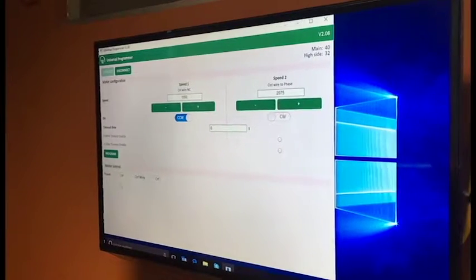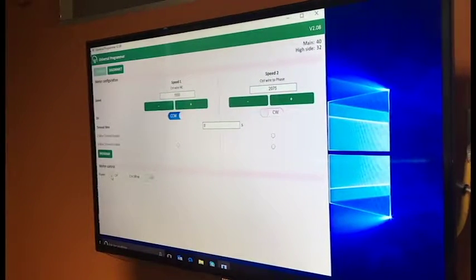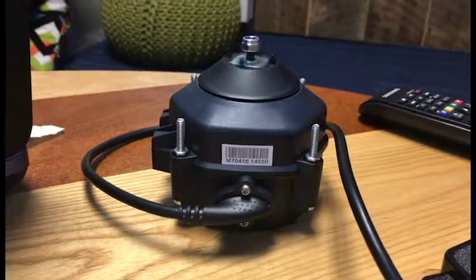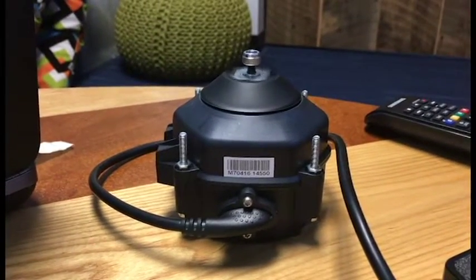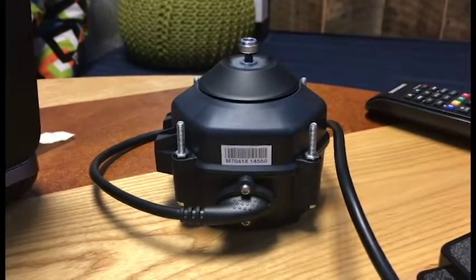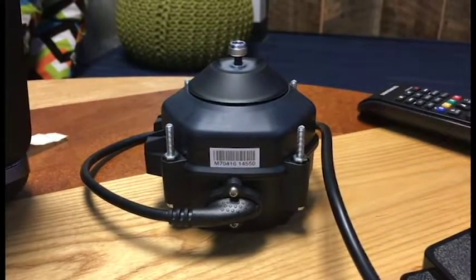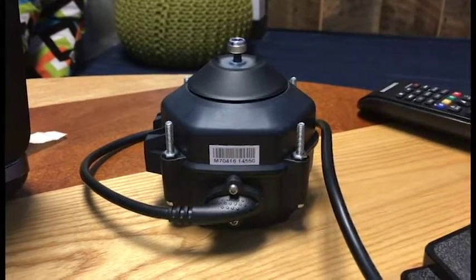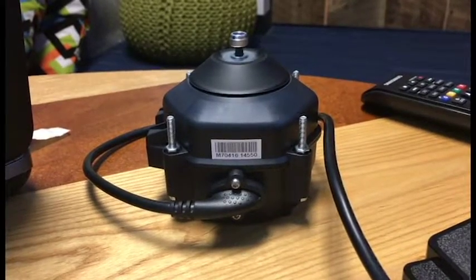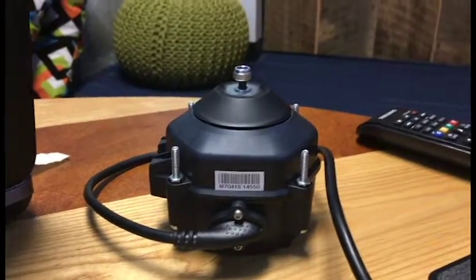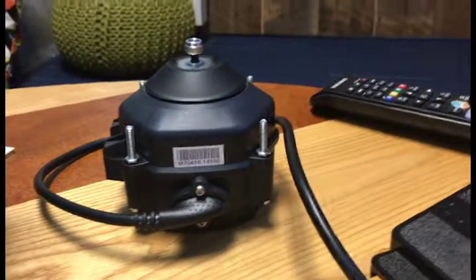So now to run the motor, just to test those speeds, for speed number one, I'll just hit this slide button, and if you look at the motor, it senses the position, and now it's going to spin 1550 RPM counterclockwise as viewed from the drive end. It has a programmed ramp time, so it'll get up to speed over a few seconds. Notice how smooth the motor is, how quiet it is. I'll stop talking for a second. Very, very quiet.